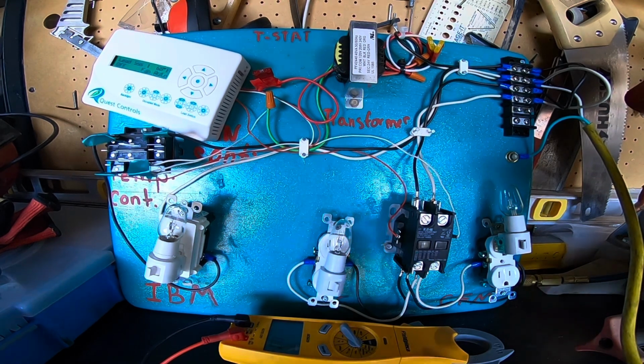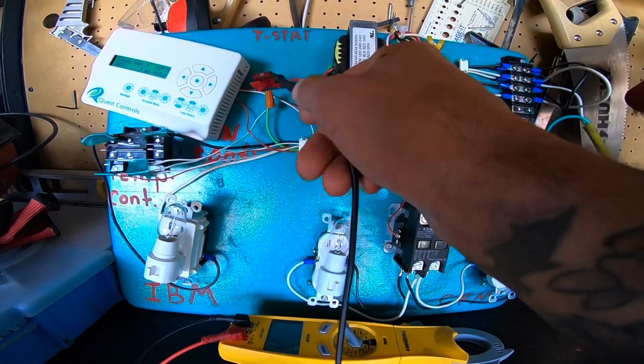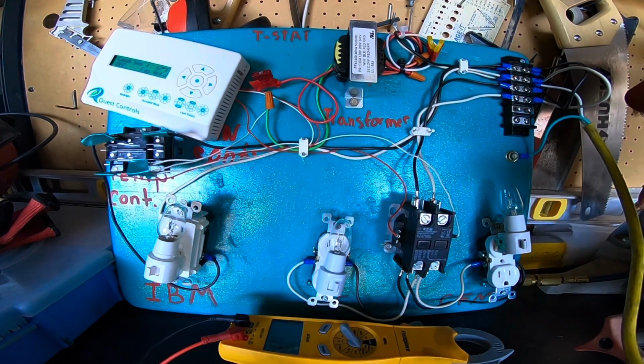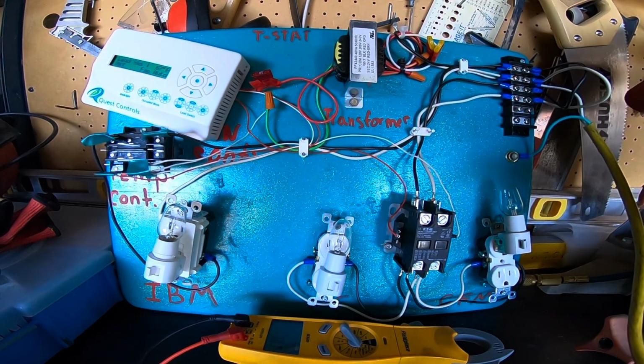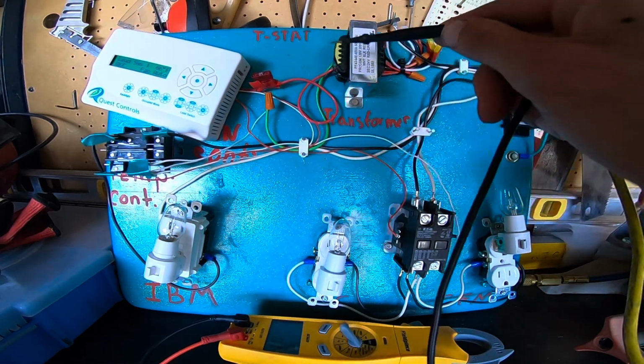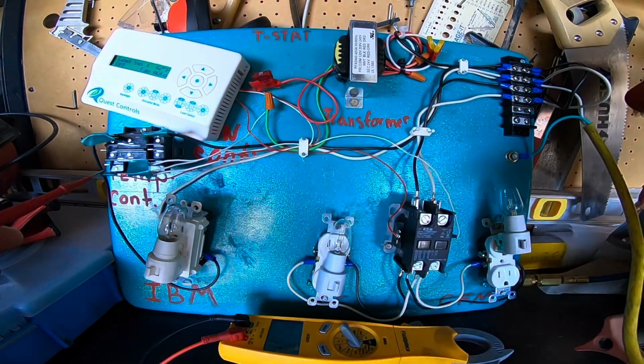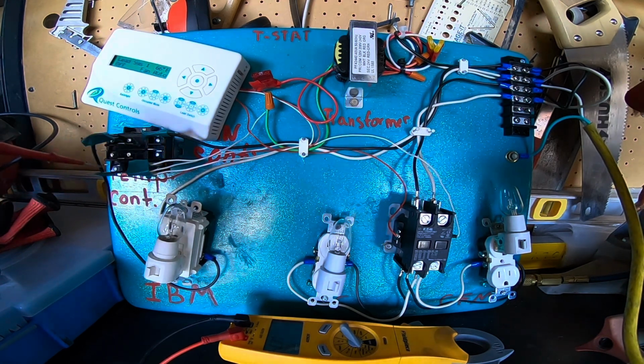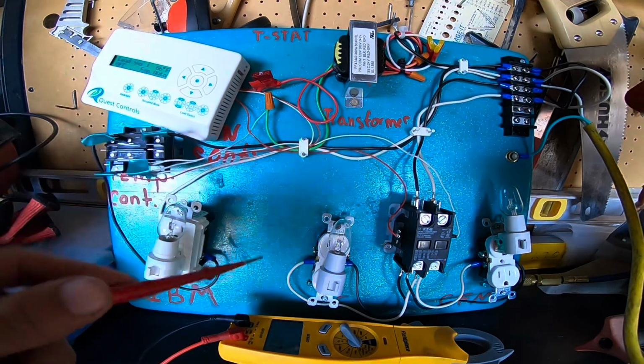One of the most difficult troubleshooting scenarios that I see is when this 24 volt fuse pops. And a lot of times in commercial air conditioning, you have CO2 sensors going downstairs and a fire system integrated into that. But my process of elimination for always troubleshooting this fuse when it pops on the transformer is I always just unplug the R from each coil. So I'll start out, if I can't figure it out and it's not an obvious short, then I remove the R from this coil, and then I'll remove the R from this coil, and I would turn it back on and see if this trips. Typically it doesn't.